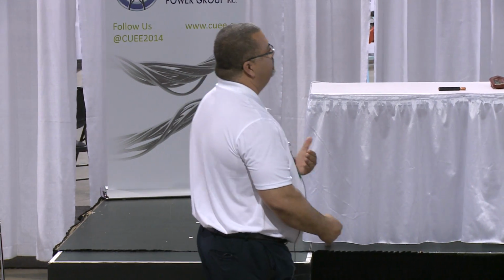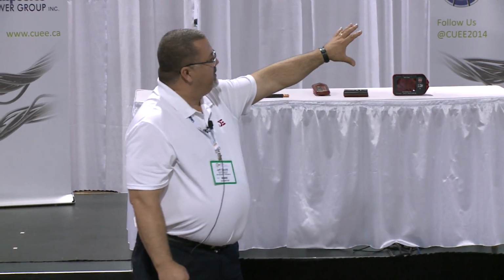It's designed for those out of normal work situations where we've had lines down during a storm or something of that nature. We don't know if they're energized or not. So in that case, we want something that will detect voltage when we're further away from it and give us a warning so that we don't walk into that energized cable. You'll notice that he's got it on a lanyard which is built into the case here. He's wearing it around his neck, and as he's walking an area, it's looking for those electric field signals to pick up and allow him to not walk into that energized cable.